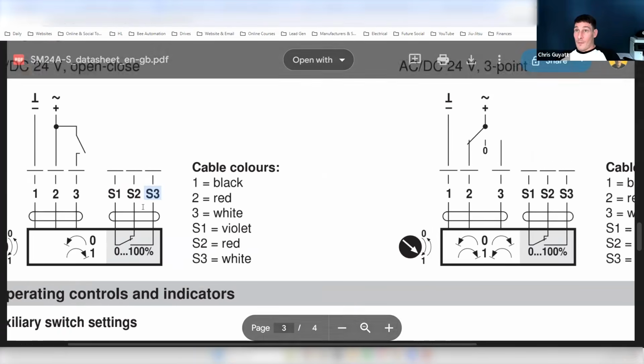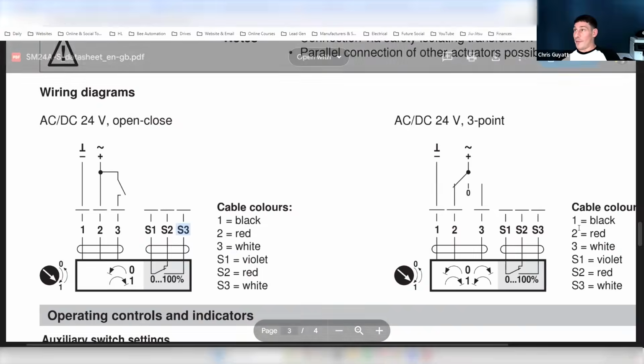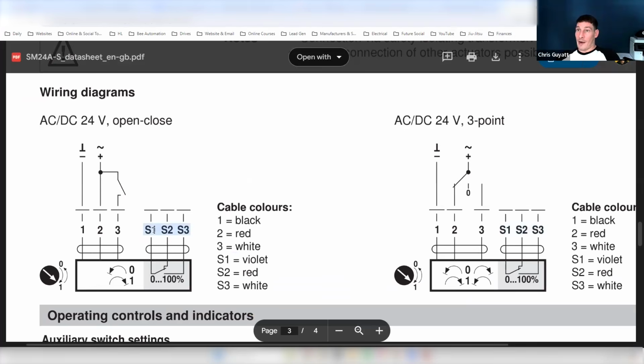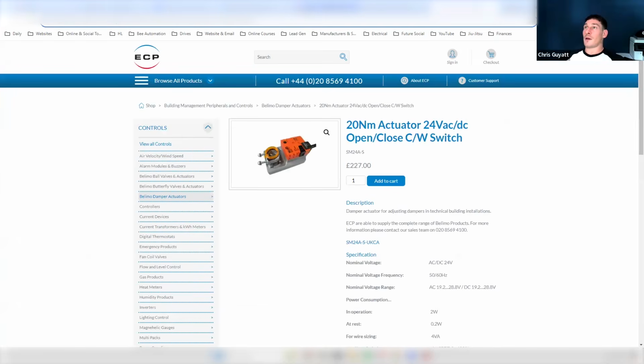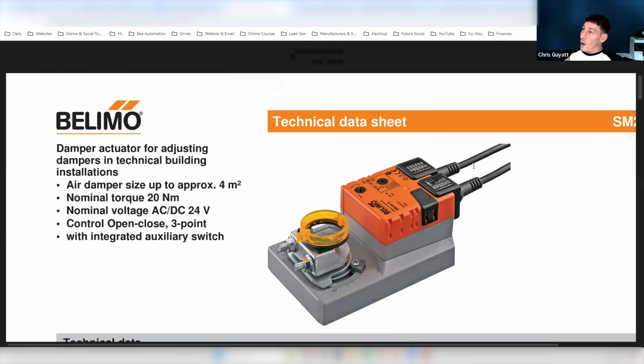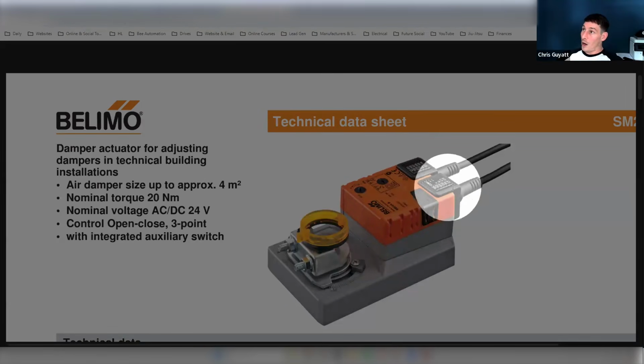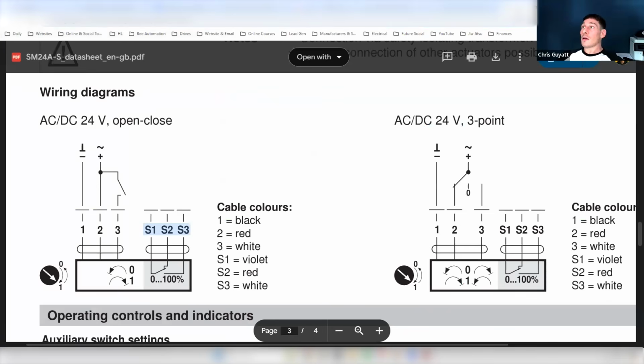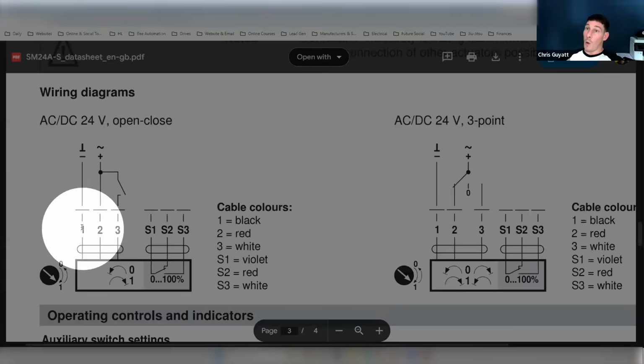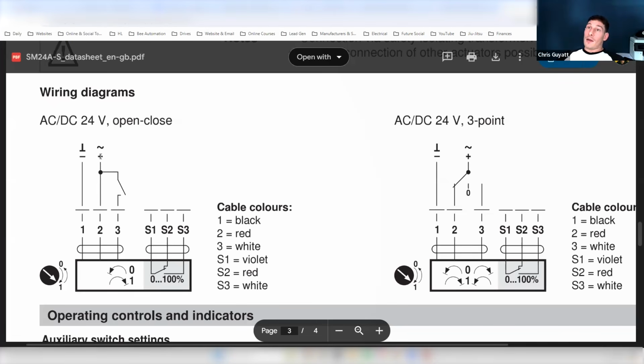So that's exactly the same thing for both ways of controlling that damper. As you can see, S1, S2, S3, it's the same. There are auxiliary switches telling us the status of the vent. Now, in terms of the control, if we're just using open and closed, so the wiring, let's just go back to a picture quickly. So we've just looked at the wiring and the cable on this side of the actuator over here. Now let's look at the wiring over on this one. So we've got our 0 volts. So 0 volts, that just goes in on 1. And then it can be AC or DC, but 24 volts. So then we've got 24 volts, a constant 24 volts that's going in on 2.